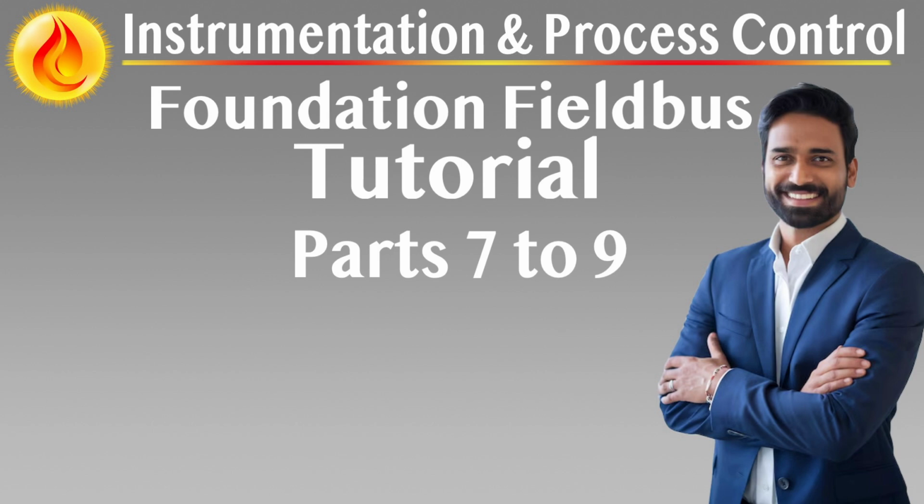Specification for Foundation Fieldbus Part 8. High-Speed Ethernet, HSE. High-Speed Ethernet HSE is the backbone networking layer in Foundation Fieldbus that extends the capabilities of the traditional H1 31.25 kbit/s segments by providing high bandwidth, plant-wide digital communication over 100 Mbit/s or higher Ethernet. Designed to integrate distributed control systems, advanced diagnostics, asset management, and enterprise-level applications, HSE bridges the field-level instrumentation network with supervisory systems using a unified and scalable digital architecture.